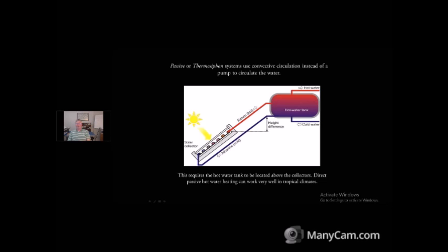You're not going to probably get the 40 to 60 psi that you're going to get out of a municipal system, but if you set it up for the lower pressure, just remember that you can get almost 15 psi out of 30 to 35 feet of drop. I've seen systems like this just put up on top of the building or up on a tower somewhere or up the hill a tiny bit and then just let gravity feed them down.